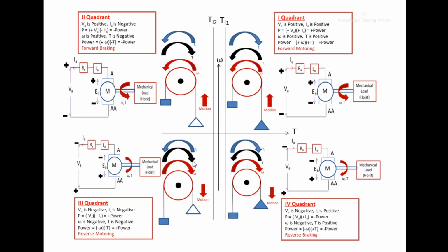So in this clockwise direction it has provided the motoring. If I want to brake or stop the motion, I have to make the opposing torque. So here the current direction is in this way. See here, the red mark. Now I want to reverse this current, because braking torque can be achieved by reversing the current direction from the motoring mode. Whatever the direction of the current is in the motoring mode, if we reverse it, we will get the braking mode.